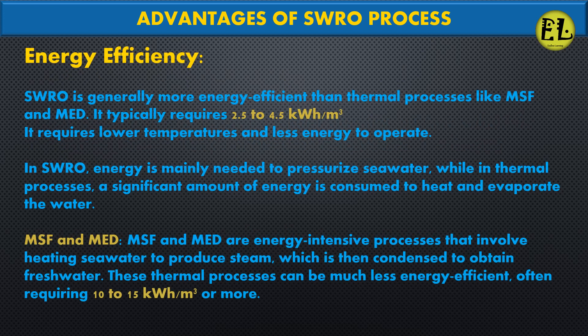Energy Efficiency: SWRO is generally more energy efficient than thermal processes like MSF and MED. It typically requires 2.5 to 4.5 kilowatt hours per cubic meter, requires lower temperatures, and less energy to operate. In SWRO, energy is mainly needed to pressurize seawater, while in thermal processes, a significant amount of energy is consumed to heat and evaporate the water.